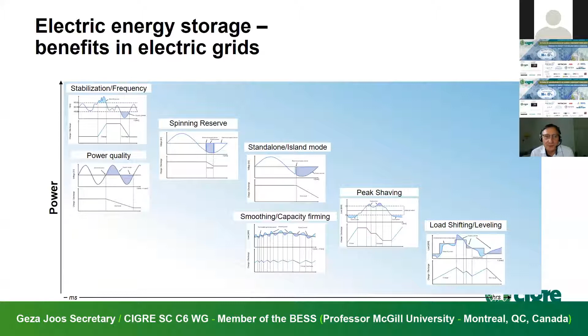The problem there is that it is essentially smoothing out the variations and not filling the voids. Peak shaving, this is load shifting - peak shaving and load shifting are in the same category. This is an important benefit. So this is a summary. Now, what is important in this slide is that yes, batteries can provide all these benefits, but they cannot provide them simultaneously. So you have to decide what your priority is at a given time and put the battery energy storage system to use for that particular application.